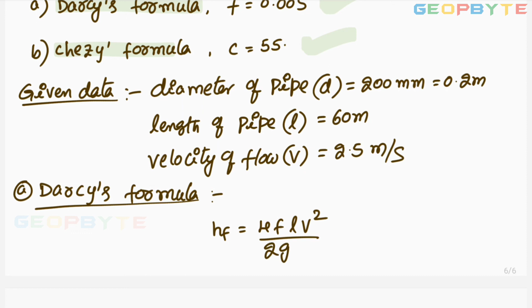According to Darcy, the head loss due to friction HF equal to 4FL V square by 2GD. The HF equal to 4 into F, given 0.005, L, length of the pipe, 60 meters, V 2.5 meter per second, by 2 into G, 9.81, multiplied by D, pipe diameter, 0.2. You simplify with calculator. I am getting around 1.91 meters. You will also get almost the same answer. Try to practice with your calculator by keeping it beside you to simplify the solution.